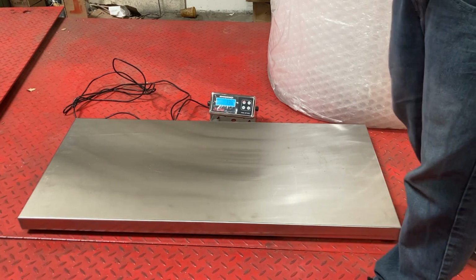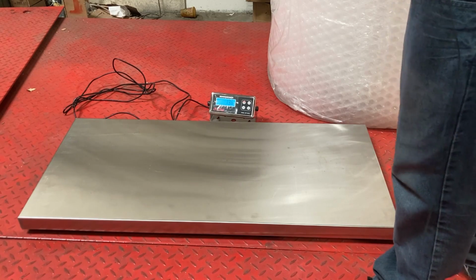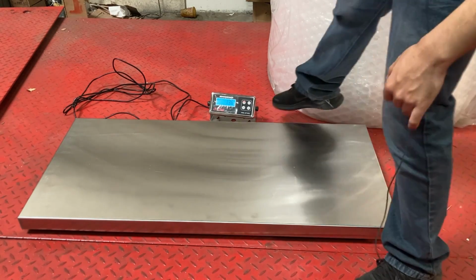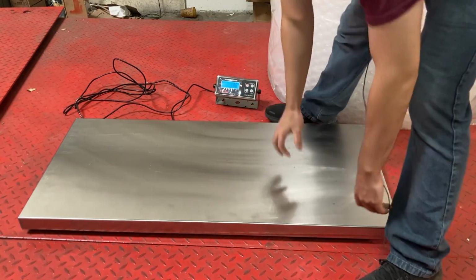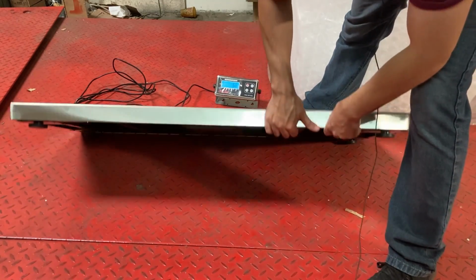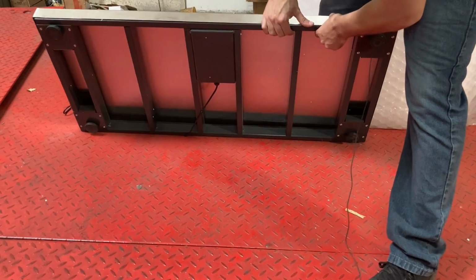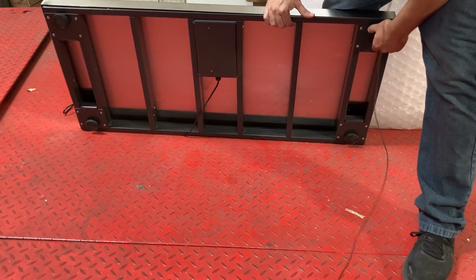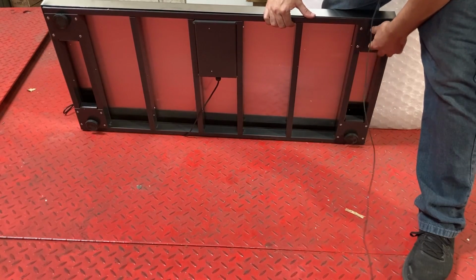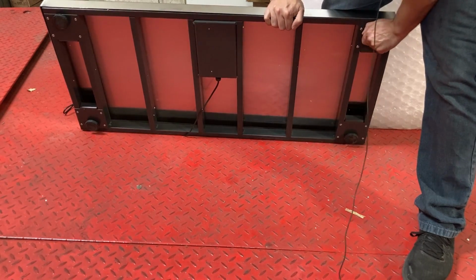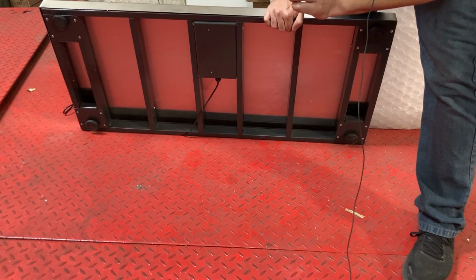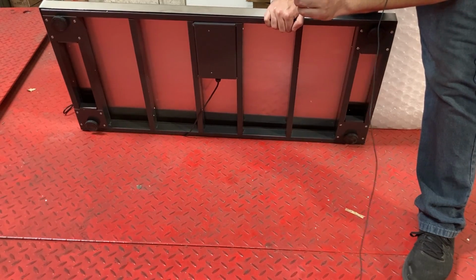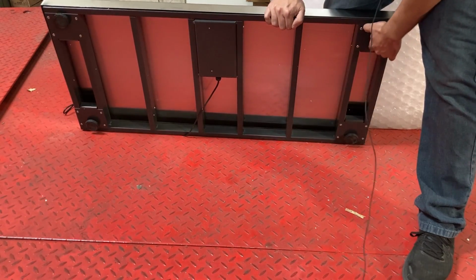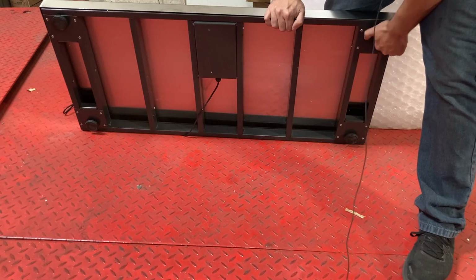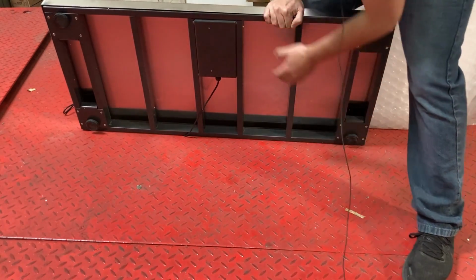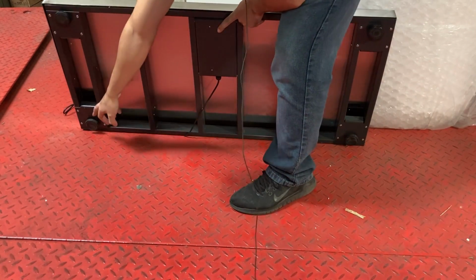And this is actually very important because I get a lot of phone calls for this and it's something so simple. But if you actually lift up your scale, you see the feet should not be screwed in all the way, right? Some people screw them all the way down and there's no travel for the load cells. So it's always giving error 6 regardless of how many times you calibrate it. You have to make sure it's leveled but not screwed in all the way. So you see my feet are not screwed in all the way in.